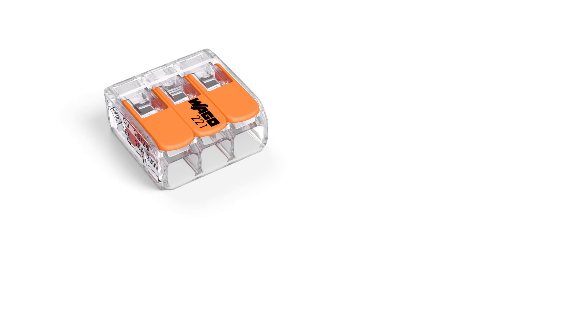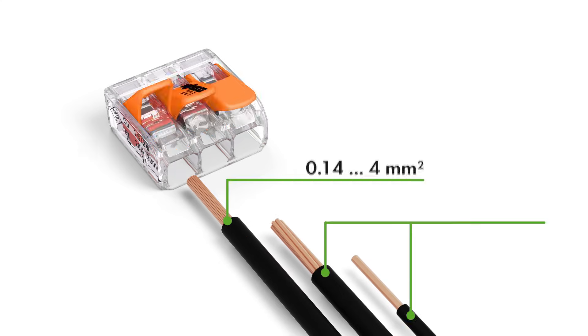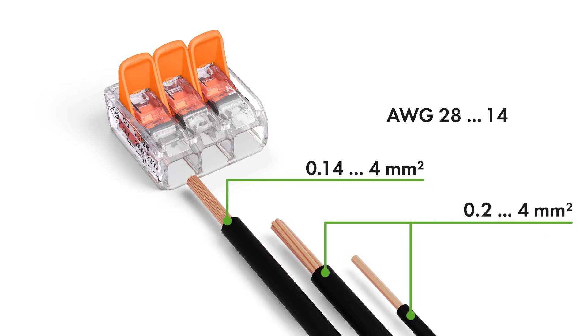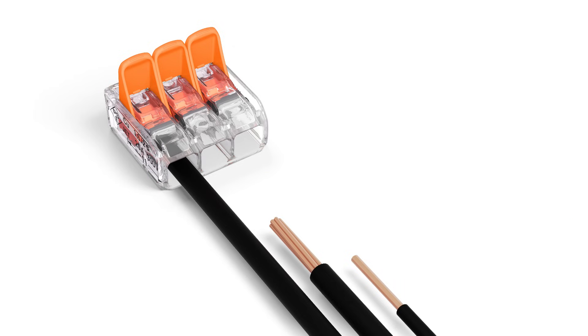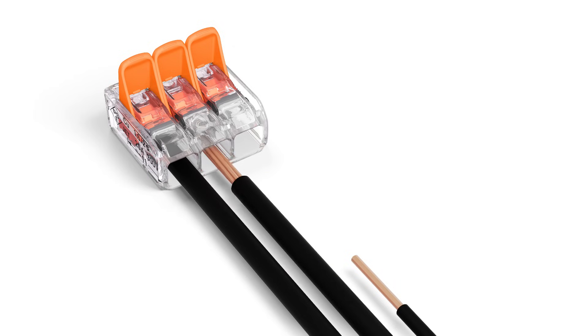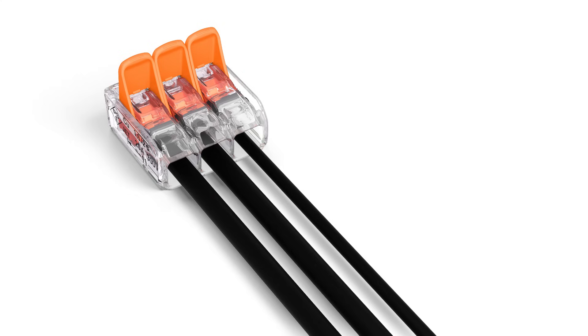The compact splicing connectors for all conductor types feature a large connection range: 0.14 to 4 square millimeters fine stranded and 0.2 to 4 square millimeters solid and stranded, 28 to 14 AWG. This flexibility permits a wide range of applications, especially when conductors of different types and different sizes are used together.